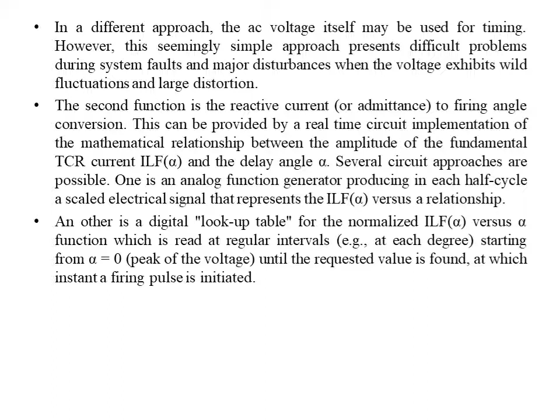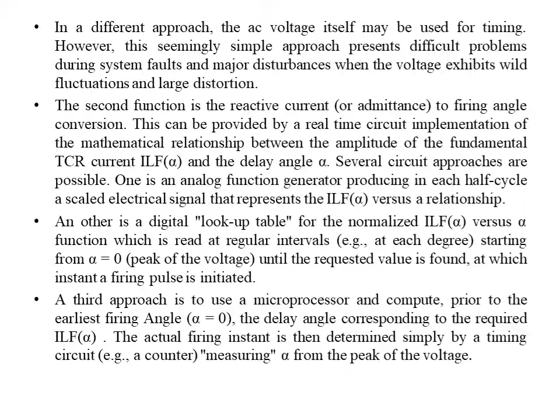A third approach is to use microprocessors and compute, prior to the earliest firing angle alpha equal to 0, the delay angle corresponding to the required ILF alpha. The actual firing instant is then determined simply by a timing circuit, a counter, measuring alpha from the peak of the voltage. So there will be a delay circuit in the microprocessor, since the microprocessor requires time to convert the analog signal to a particular digital signal from the lookup table.